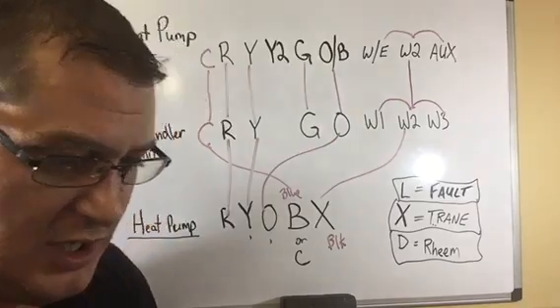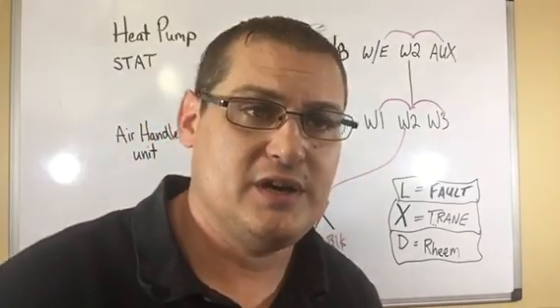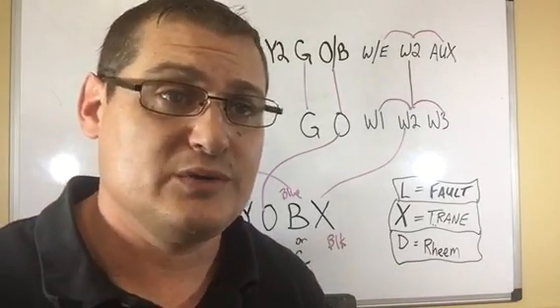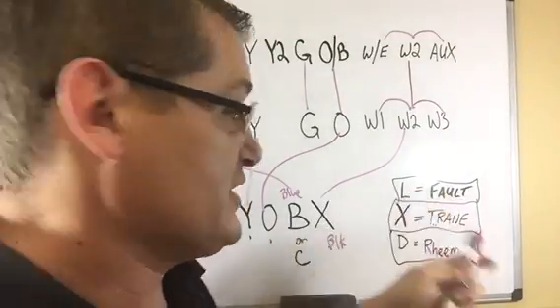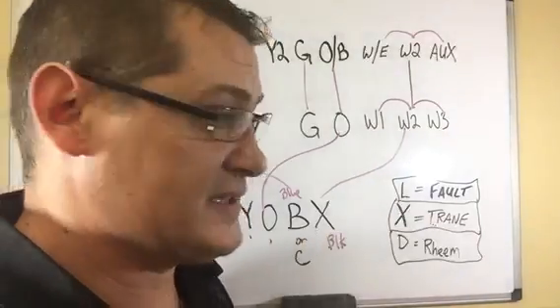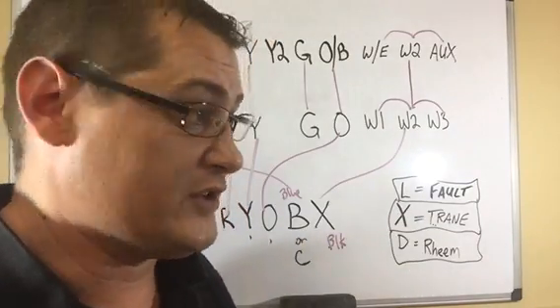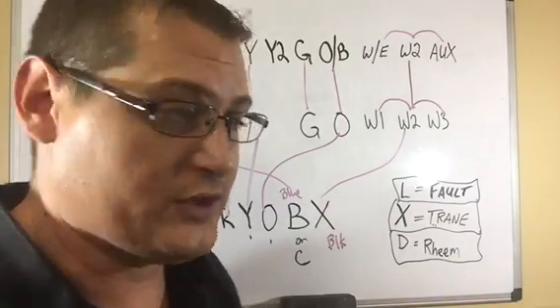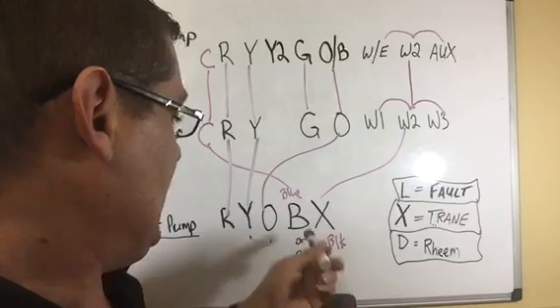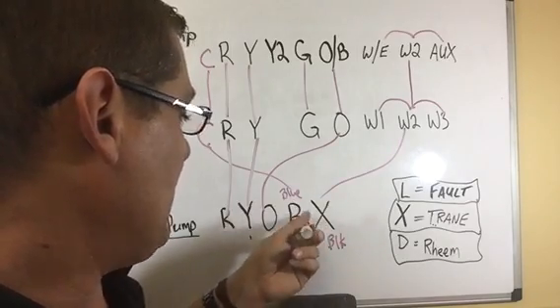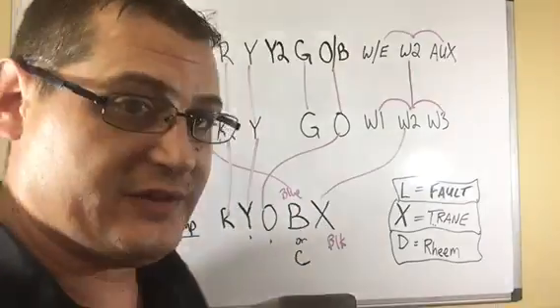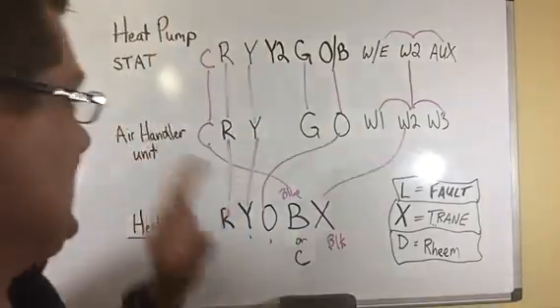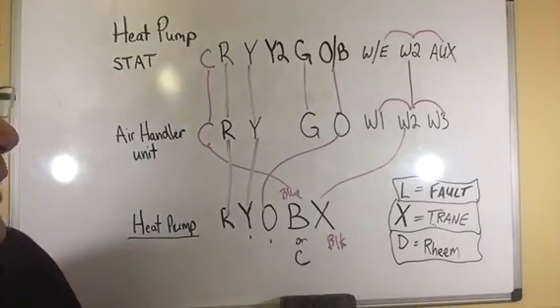Hopefully I didn't confuse you on what we were talking about. I'm just trying to get you to understand you just need to know what the terminals do. It's important to know that L is a fault terminal, X is the signal to call for the strip heat, D on that particular Rheem brand is the signal to call for the strip heat, and knowing that they're using this blue wire called B for common. As long as you know what it is, then you can wire it up properly and easily. That's a brief overview of heat pump thermostat wiring.